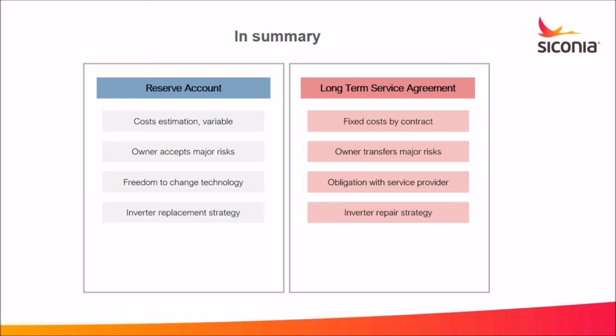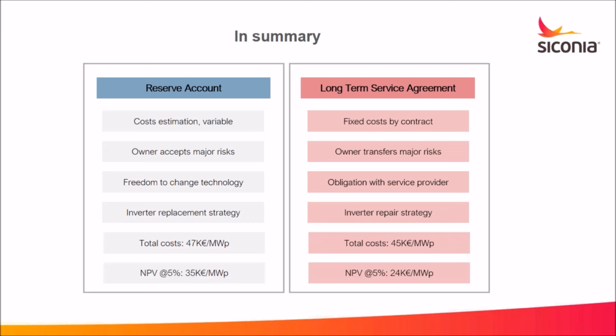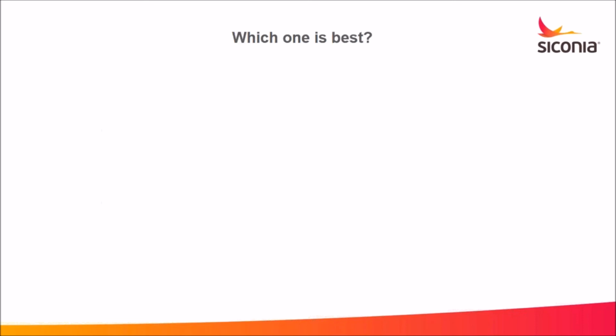So we could say that the reserve account option is an inverter replacement strategy, while the service agreement is an inverter repair strategy. Total cost, as we've seen, is quite similar, but the net present value of the reserve account is 35, while the service agreement is 24. It makes sense because the payments for the reserve account are done during the first half of the plant lifespan, and the service agreement payments are in the second half.